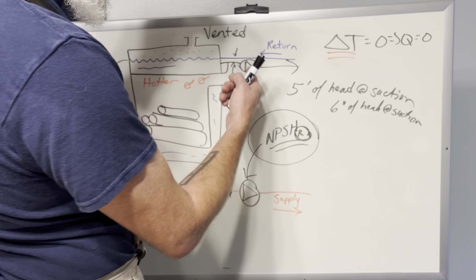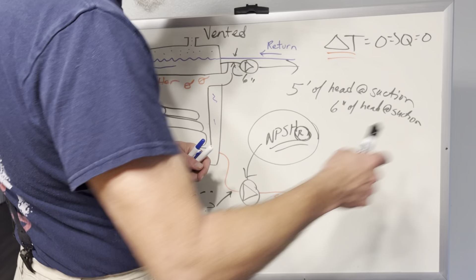There are times where you want it to be up here. You may be all downhill. Your boiler may be 300 yards away and 100 feet down a hill in a valley, and you're pumping the water up here. All of that changes the elevations of equipment on a vented system. But that's two reasons why you potentially want to be pulling from the bottom.